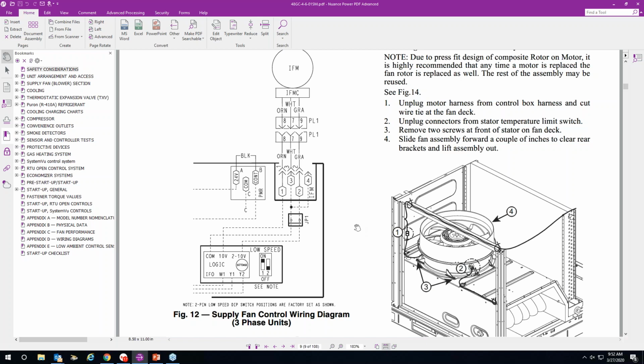So one of the first things I would do is put it in fan continuous mode, so I know I've always got a signal to the fan. And I would check my orange wire to either chassis ground, to the white wire, or one of the spade terminals on the board that we use for setup. So do I have 10 volts DC here? Not 15, not 8, but 10 volts DC. So if I've got that, it's like, okay, the motor controller is generating the 10 volts. Now, do I have a signal back? I need something, 4, 5, 6 volts. I need something between, say, 4 and 10 volts DC coming back on the gray wire.